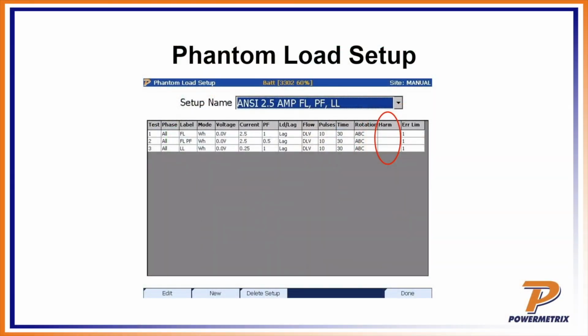In the PowerMaster, Jared's going to show us a screenshot of the phantom load setup. If you want to use some of these harmonic waveforms, there is a setup screen in there. If you look at the column that says harmonic, you can actually enter into that field, and there's a drop-down box in that harmonic cell. There are 3 options there: sine, phase fire, and multiple zero crossing.